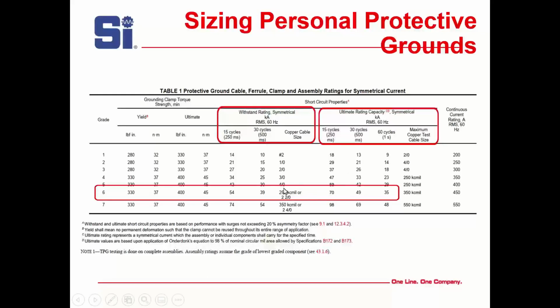And then looking at the ultimate rating, you can see it's very high, 70,000. If I look at the withstand rating, I see it's quite a bit lower. So it's just a margin for error. And I have to put up two grounds that are the same size, same impedance, and the same length. That's the way to handle it. Don't just do one and think it's good.